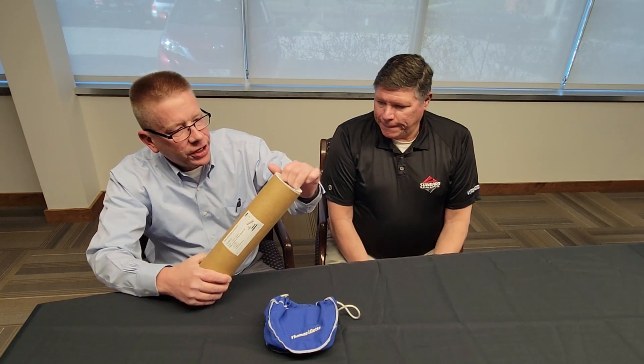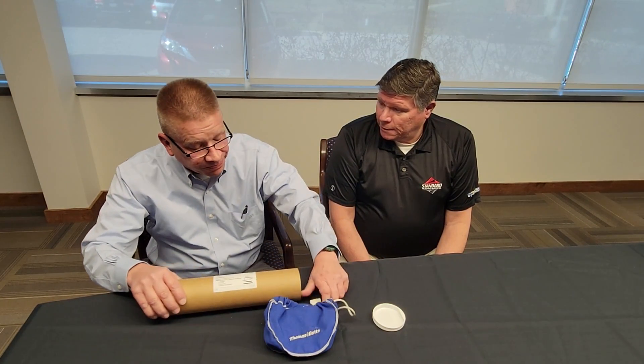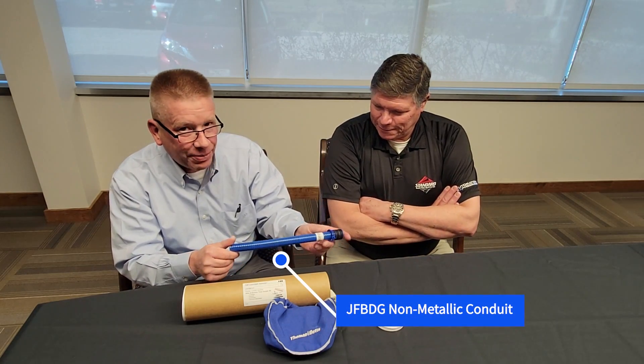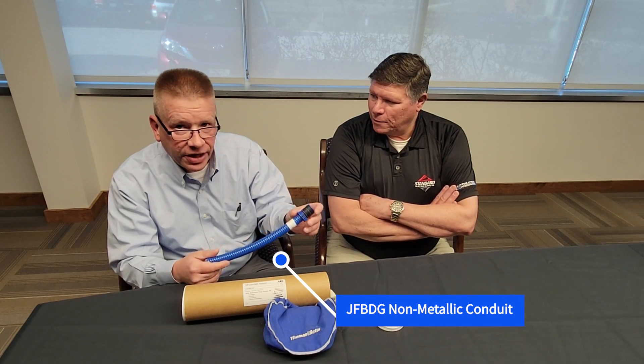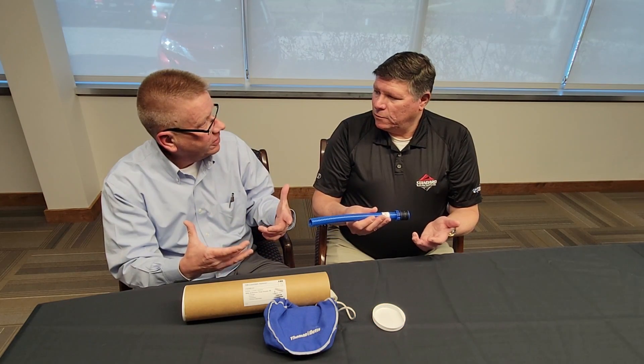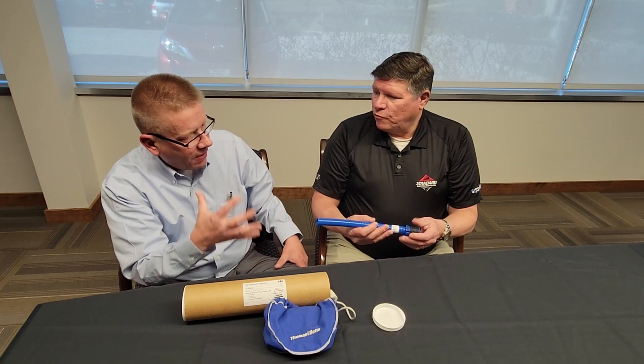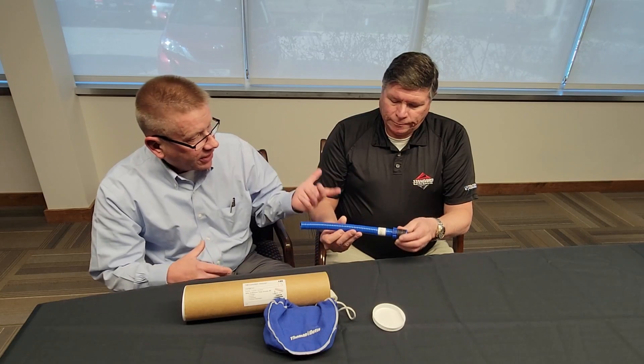So I brought some of our solutions to prevent liquid ingress into your electrical system — commonly known as liquid-tight conduit. The first one we have is our JFBDG, which is a non-metallic conduit over-extruded with a coating and our non-metallic fitting. As a system, it's rated IP69, which is critical for wash-down — very high pressure type applications. So that's our non-metallic solution.